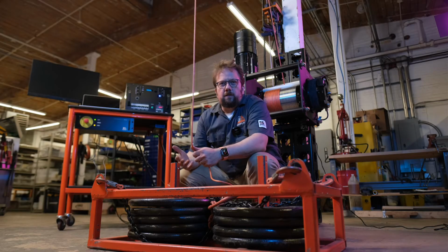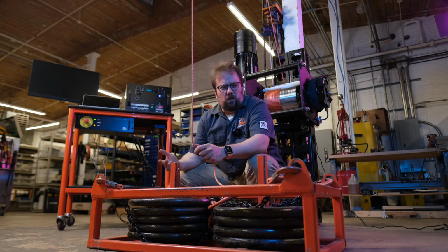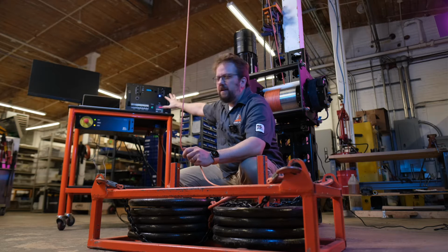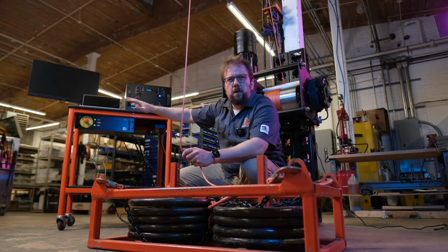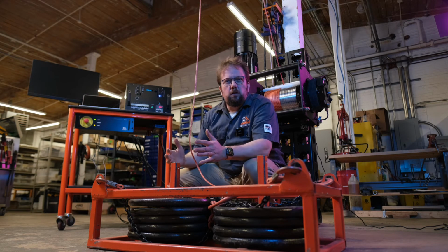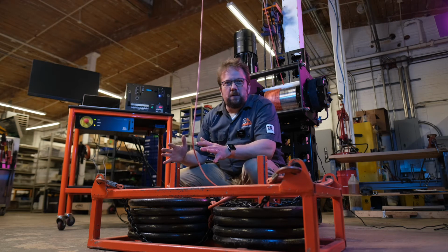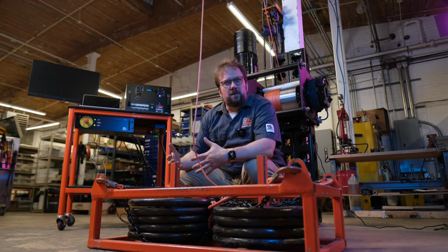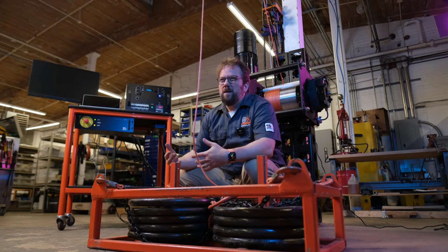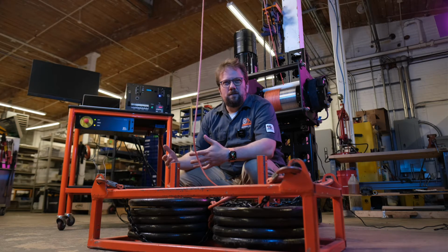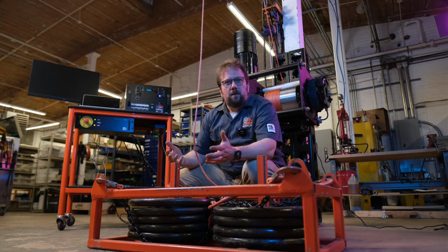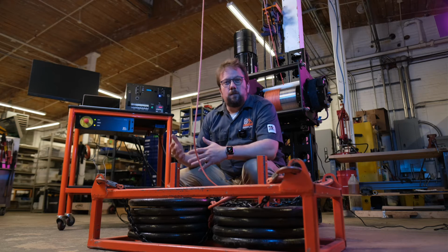I think it's fair to ask first, why do we need limit switches at all? Don't we have encoders on the motor and a fancy controller and all sorts of software that's supposed to put the load from the hoist exactly where you want it to go? Yeah, but sometimes that doesn't work. And you might think, the limit switch almost seems redundant. It is. That's actually part of the point. We need the redundancy when some of the other stuff doesn't work so well.